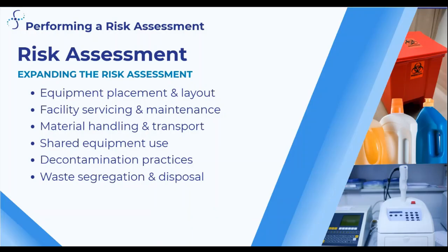When multiple research groups use the same equipment, like centrifuges or water baths, there's a risk of cross-contamination if users don't follow consistent cleaning and decontamination procedures. Maintenance work may introduce personnel unfamiliar with biosafety risks or create opportunities for accidental exposure if the equipment is not properly decontaminated beforehand. It is critical to assess whether effective disinfectants are selected for the agents in use and whether protocols are followed consistently. Inadequate decontamination can leave residual hazards behind.